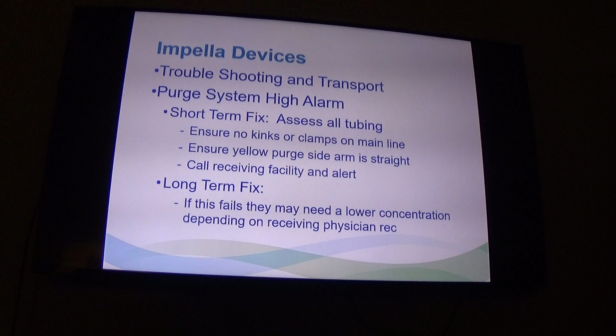If there's air in the purge line, you'll have to select the D-air purge system and follow the prompts. It'll ensure that your purge fluid is vertical. If it's hanging down over the side of the bed, you're going to get a problem - pick it up, that's enough sometimes to solve the problem. Ensure your tubing isn't kinked.